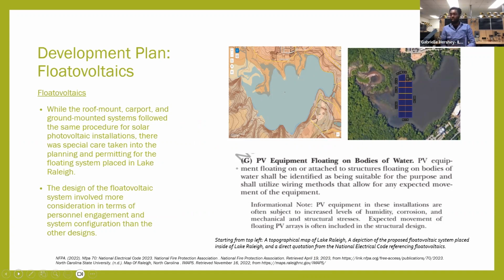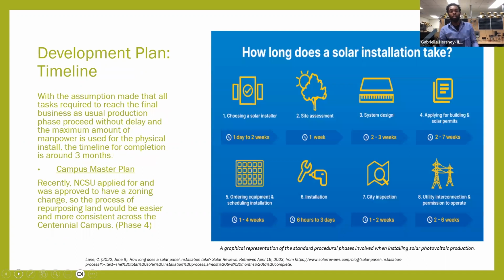While the ground mount, roof mount, and carport systems followed the general procedure for solar installation, there was specific verbiage for floating PV equipment listed in the National Electric Code's 2023 edition. It basically states that if you want to design a system floating on water, it has to be specifically designed to meet racking configuration, so that increased humidity from being on the water doesn't affect the racking in the system as a whole. For our timeline, we used a residential timeline, as shown in the figure, but it's still applicable to commercial installations since these are the roots of installing solar.